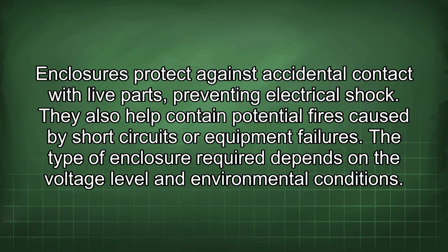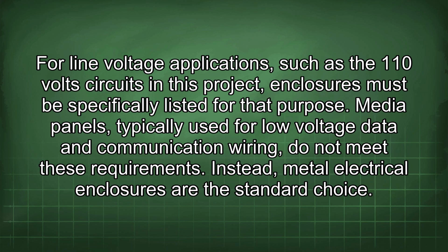Enclosures protect against accidental contact with live parts, preventing electrical shock. They also help contain potential fires caused by short circuits or equipment failures. The type of enclosure required depends on the voltage level and environmental conditions. For line voltage applications, such as the 110-volt circuits in this project, enclosures must be specifically listed for that purpose. Media panels typically used for low-voltage data and communication wiring do not meet these requirements.